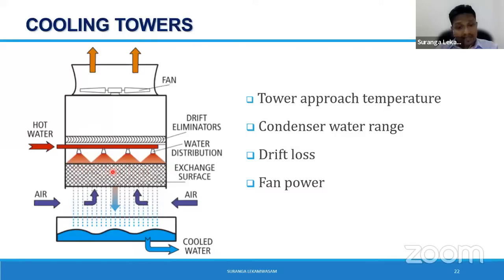There will be a certain amount of water evaporation. That evaporation latent heat is absorbed by the same amount of water, and the water collected at the basin, its temperature drops because of this evaporation. Similarly, you have to understand, because of this evaporation, there is a certain amount of water loss. We call it evaporation loss. So this is how your cooling tower works.